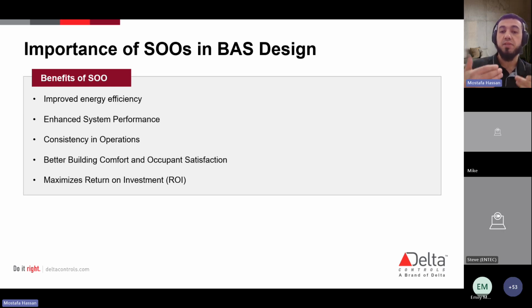And finally, last but not least, and this is extremely important as a designer when you're dealing with an owner or a customer, by ensuring a proper sequence of operation, or ensuring that your system operates efficiently, you're going to minimize energy costs, and you're going to get your customer the highest ROI, return on investment, right? Because you can spend the money now, but with no data coming in, with no information on how the building is actually performing, then it's just money wasted, right? You spent a lot of money on automating all these systems, throwing controllers everywhere, hardware, field devices, but you don't really get any information back. It's really just a waste of money. So there's a lot that goes into it. And again, as I mentioned, sequence of operation is not the end goal of optimizing buildings.